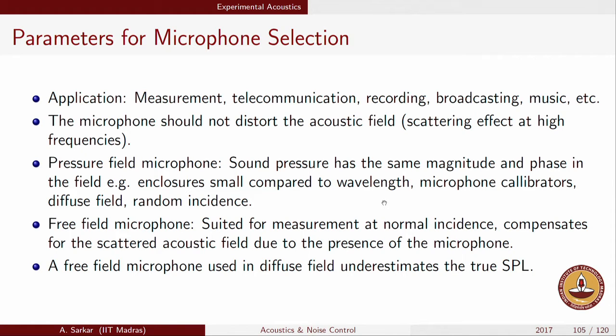The pressure field microphone, which has a slight variant called the diffuse field microphone, is used when sound pressure needs to be measured in a small enclosure. The diffuse field microphone, as the name suggests, is more appropriate in a larger enclosure. Free field microphones are typically used in anechoic chambers, where they face only one incident wave.